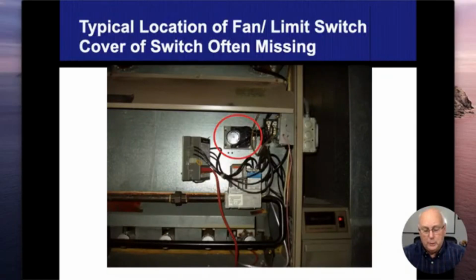So there's an actual picture of what it looks like, and that's what is circled right in here. Typically, it's going to be between two of the heat exchangers. So if I go down on the bottom, that's where the burners are. That has its own heat exchanger coming up here. That's another heat exchanger and another heat exchanger and so forth. The air is going to flow between the two heat exchangers, and that's where we're going to find this temperature sensor that's going to be in the circulation air, the air that we breathe. All right.